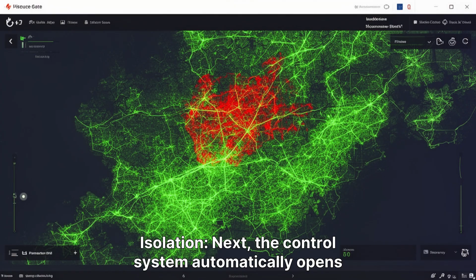Let's walk through what happens when self-healing kicks in after, say, a tree limb knocks down a line. Fault identification: the system first detects that something's wrong. AI algorithms analyze the sudden changes in electrical measurements to pinpoint the location. Isolation: next, the control system automatically opens switches around the faulted section, isolating the damaged segment so the rest stays intact. Reconfiguration: the system then looks for alternate paths, closing other switches to reroute power around the broken section. Restoration: power flows again to all customers not on the faulted segment - everyone else is back online, often within milliseconds.